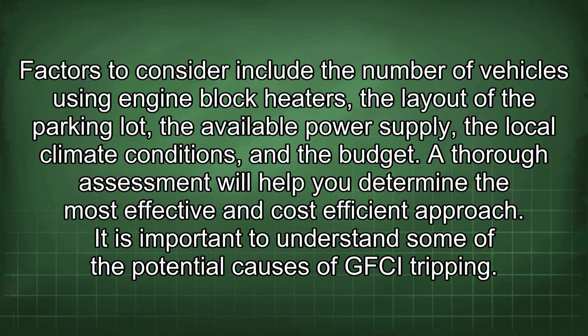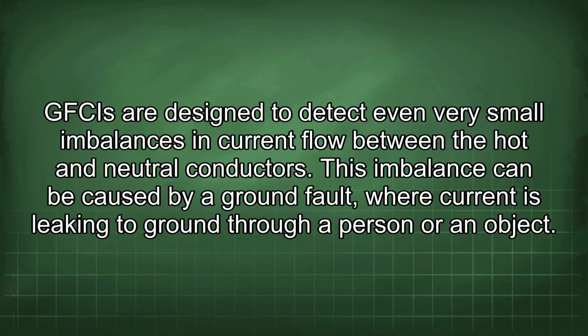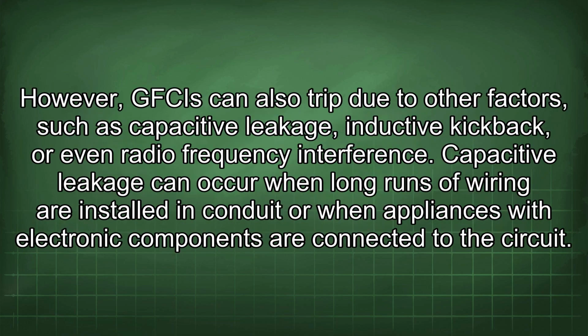It is important to understand some of the potential causes of GFCI tripping. GFCIs are designed to detect even very small imbalances in current flow between the hot and neutral conductors. This imbalance can be caused by a ground fault, where current is leaking to ground through a person or an object. However, GFCIs can also trip due to other factors such as capacitive leakage, inductive kickback, or even radio frequency interference. Capacitive leakage can occur when long runs of wiring are installed in conduit or when appliances with electronic components are connected to the circuit.